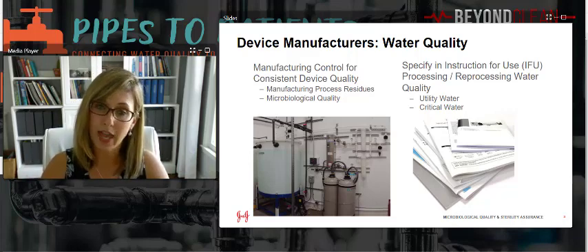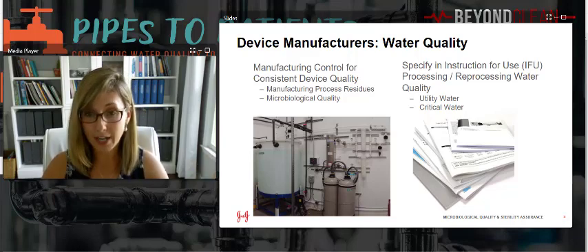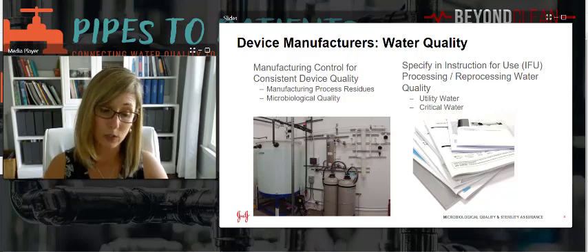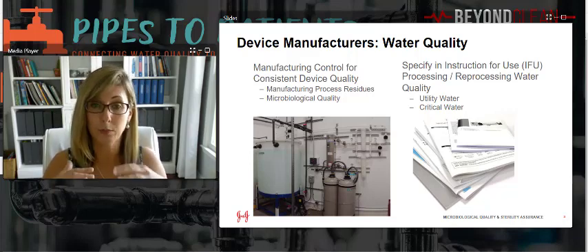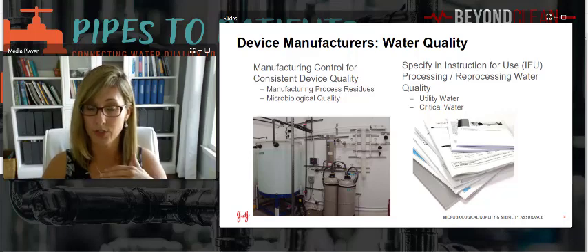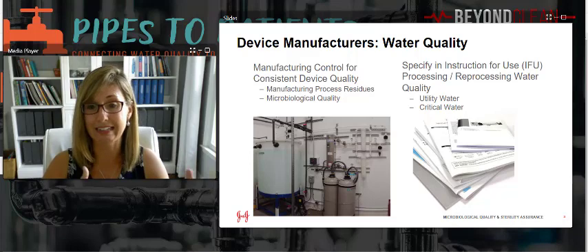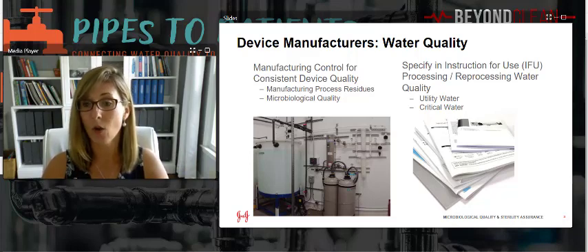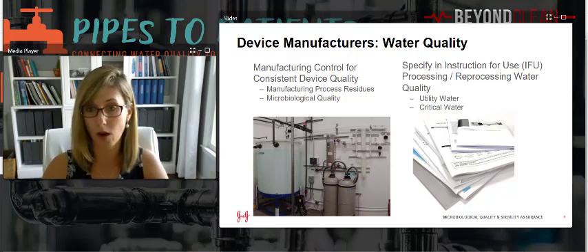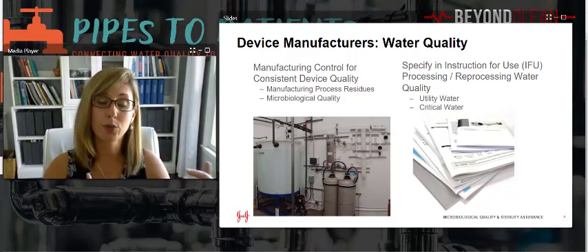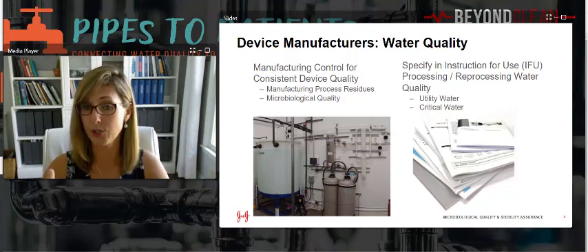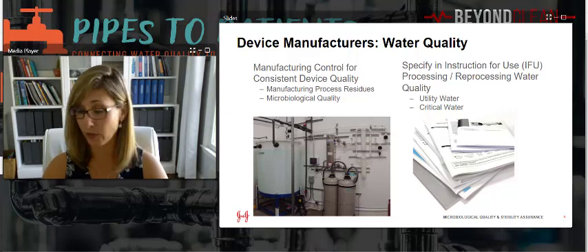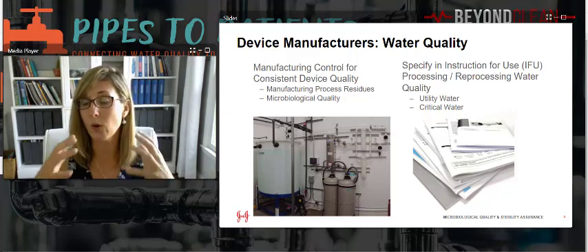So as I mentioned, manufacturers have a responsibility for water quality when we are manufacturing those medical devices, whether single use or reusable. So within our manufacturing processes, we also have to maintain control of our water systems, and they're designed to deliver that consistent water quality that maintains what we anticipate to be the right quality of water for the process to maintain the microbiological quality, which includes the chemical quality of the product that we're manufacturing. So we do a lot of routine monitoring of both the water system as well as finished product to make sure that the devices that we're delivering, again, whether single use or reusable, are of the right quality when they get to the customer.